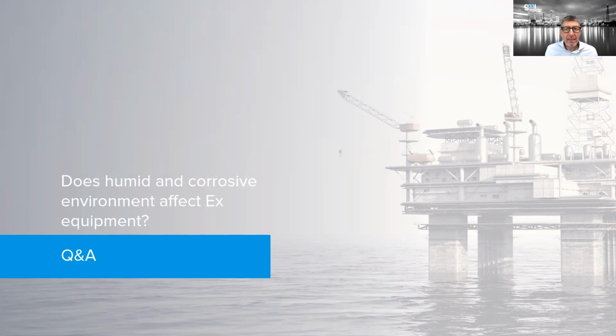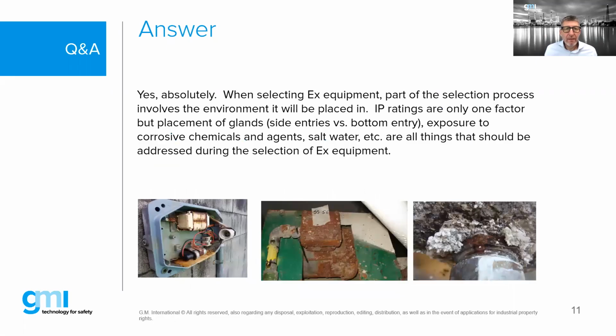I'm sure that it does. And here's your answer, some pictures you've taken through your inspection, right, Bob? Yeah, absolutely. You have to take into account the environmental condition and where you're going to be placing the EX equipment. So the picture in the middle, that's actually a zone 1 area, and that's a motor. And that motor had only been there for about 2 years. So you can see corrosion can be extremely devastating to EX equipment.